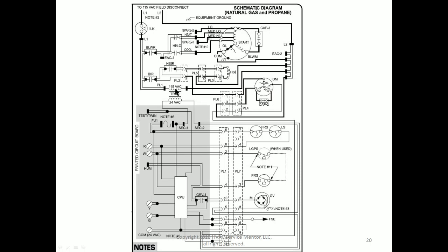Whenever we look at a ladder diagram, we look at the transformer first. That's the first thing we want to find because we do have two voltages, and there it is right in the middle where it should be. The next thing we need to find is the power supply. The main power coming in is right up here at the top of the diagram. So on a ladder diagram, this tells me that everything between the transformer and the power supply is high voltage. It's all 115 volts AC. So everything up here is 115 volts. Below the transformer, everything down here is 24 volts.